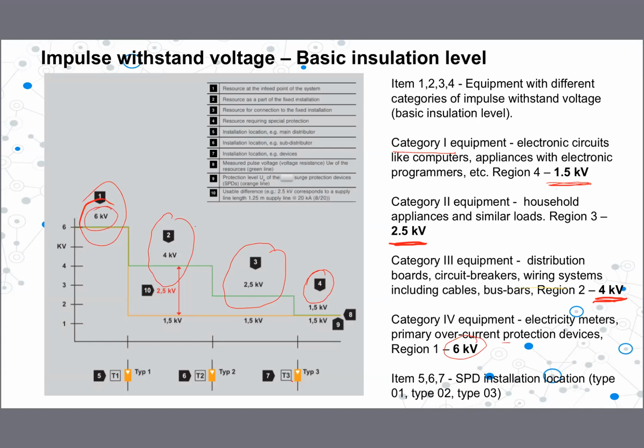insulation level, right? So now when you install surge protection devices, you can see here, type 1 surge protection devices are installed at the entry point. Then at the SPDs, type 2 devices. Then final terminal equipment, type 3 devices, right? So then your type 1 SPD should be able to handle this 6 kilovolt voltage level. It should not let the voltage level go up beyond this one.